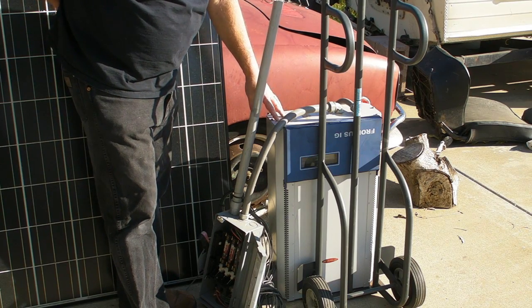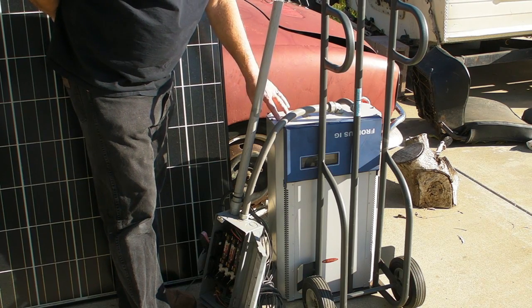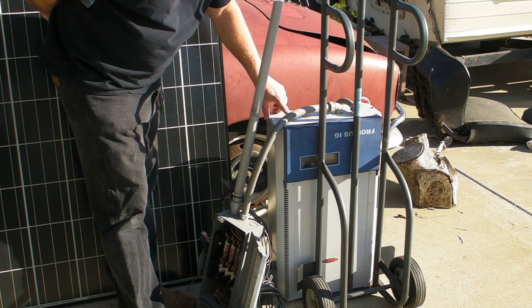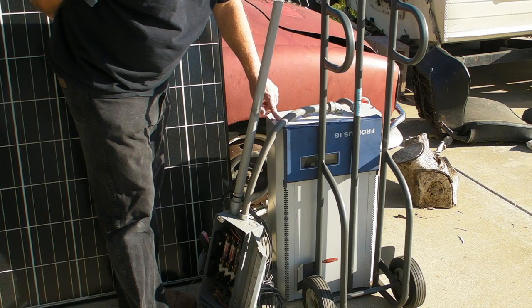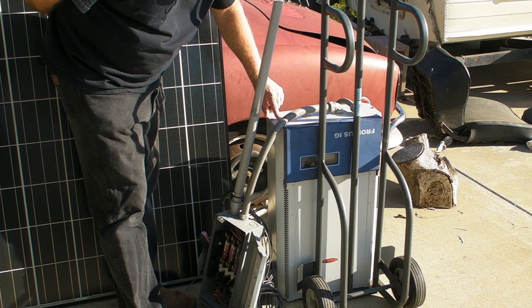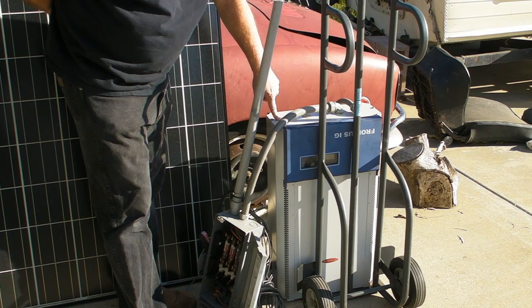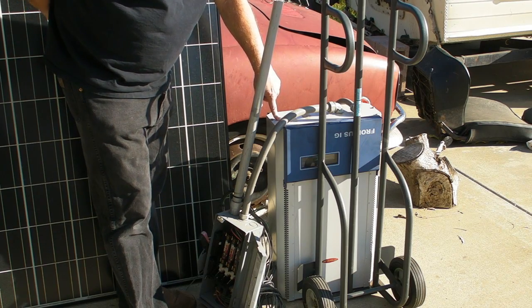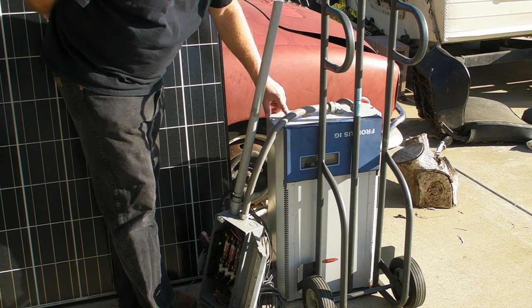So 7 amps, 7 times 5, 35 amps. So it's looking like output fault current is 35 amps. So 30 amps is current protection. Output power is 5,100 watts. So it's a 5 kilowatt system here.